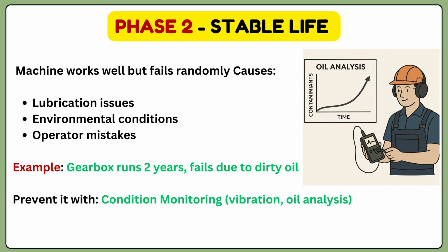So yes, we can avoid this if we use the proper condition monitoring technique here, for example vibration analysis or oil analysis. In this case, if we collected oil samples regularly and did the analysis, we can find well ahead that this oil is contaminated, right?